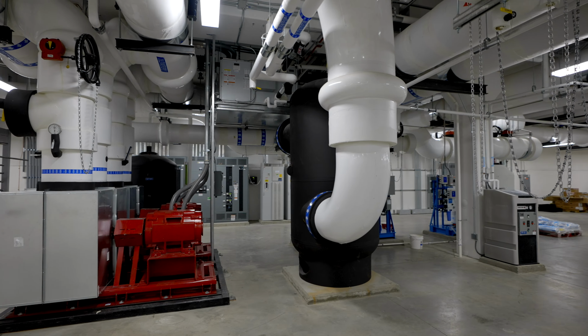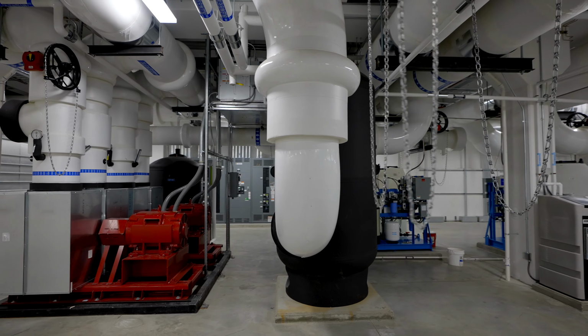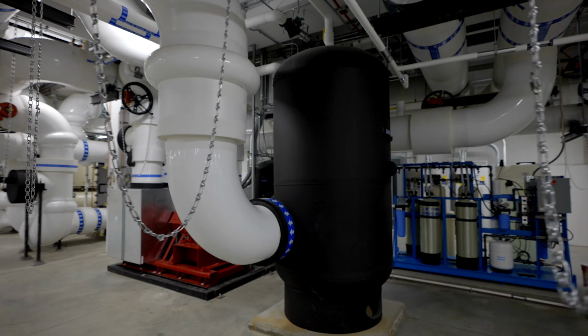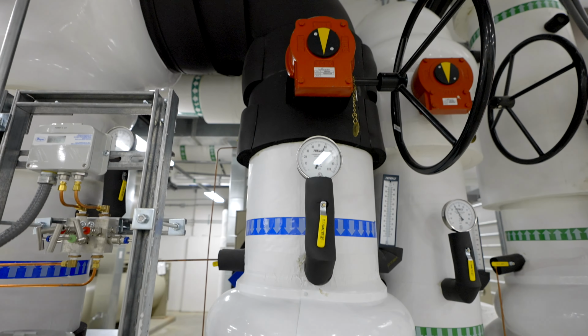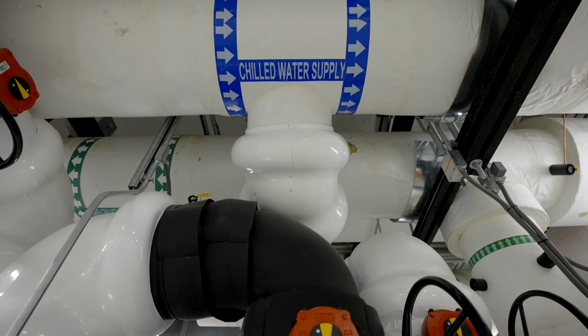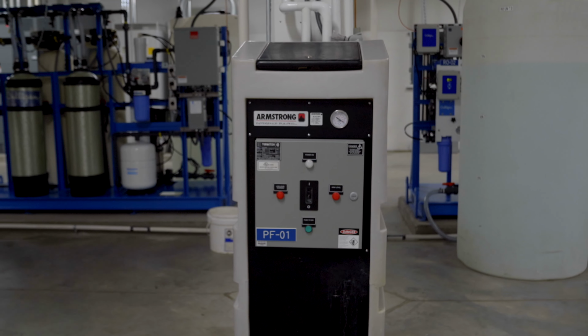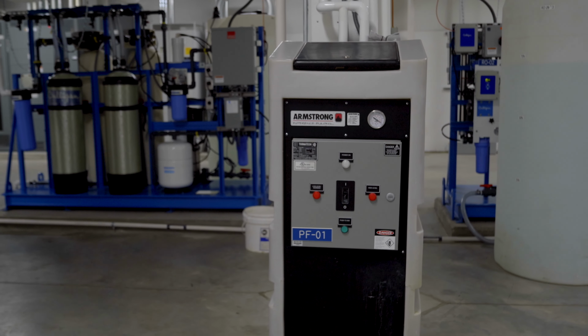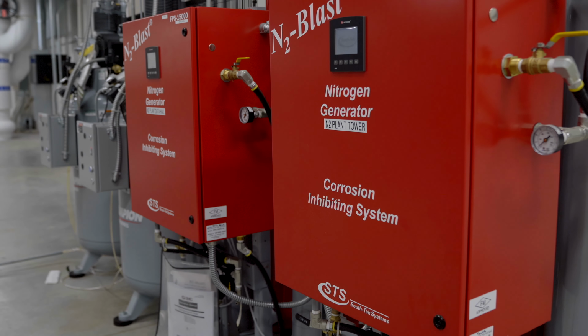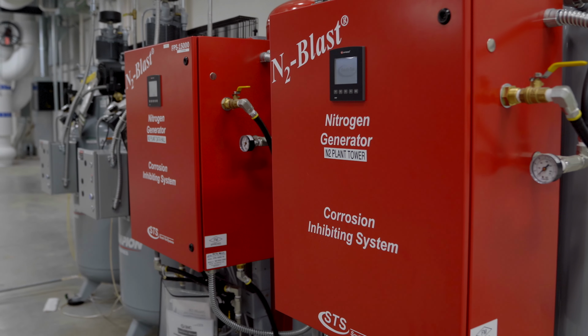The site also houses a 260,000-gallon city water harvesting tank and a 120,000-gallon cistern that collects rainwater to support backup cooling. All chiller controls are fed from 2 independent UPS-backed sources, and their emergency generator-backed pumps will restart within 30 seconds upon loss of utility. These are just a few highlights of the robust mechanical infrastructure that supports you and all of our customers.